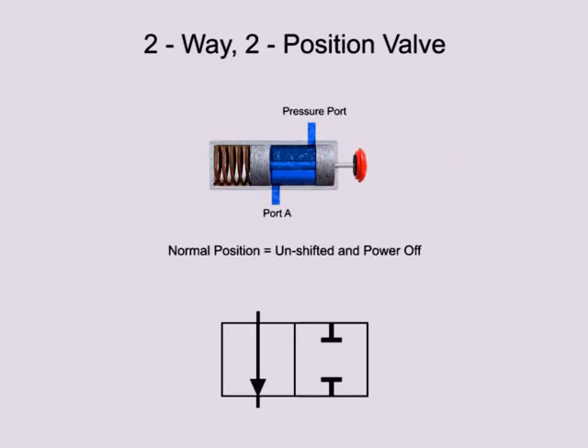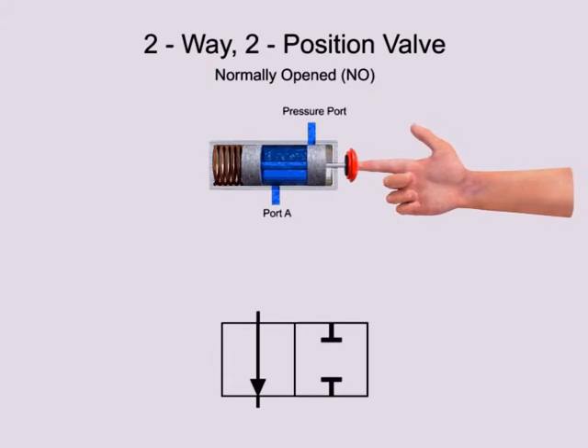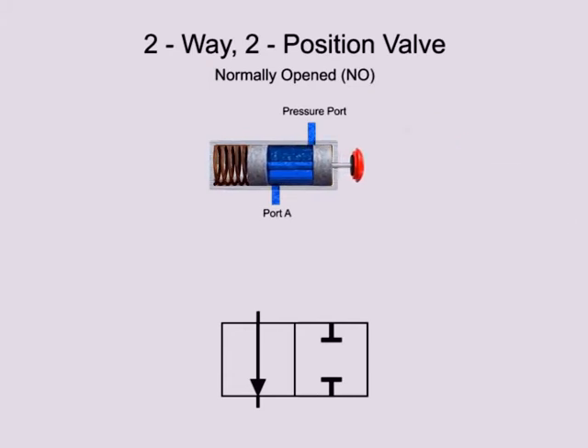The terms normally opened and normally closed are used to describe the condition of a valve when it is in the normal position. For this valve, the normal position is position 1, which allows unrestricted fluid flow through the open ports. Therefore, this valve is a normally opened valve. Additionally, this valve is a spring return valve, meaning that after it is actuated, a spring returns the spool to the normal position.